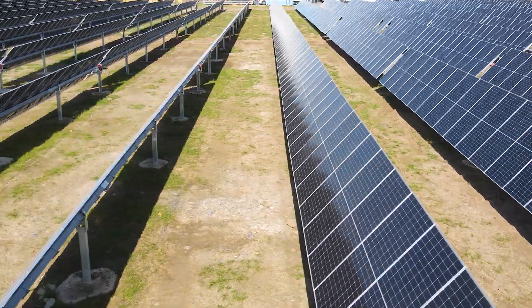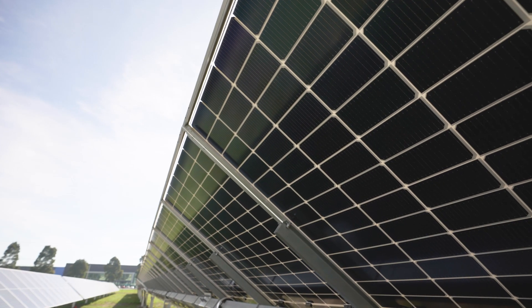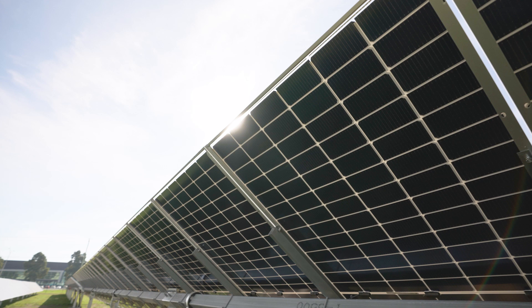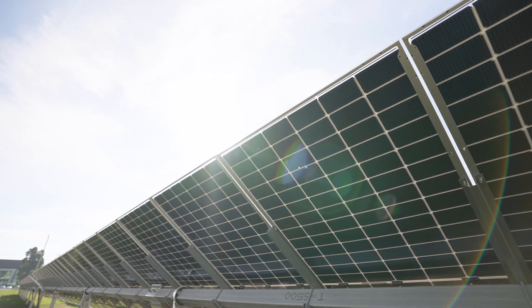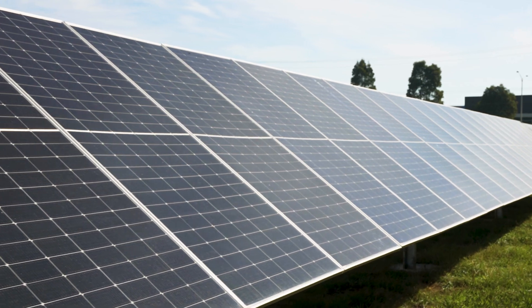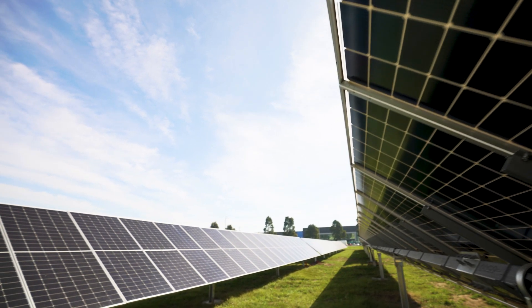One other important element of increasing the efficiency of this system for AmeriCold is the selection of panels. Above me you'll see the panel we've used — this is the Astronergy 625 watt and it's a bifacial panel. These are important to use in ground mount systems as they allow for reflection from the ground back into the panel to create more of an uplift in efficiency.